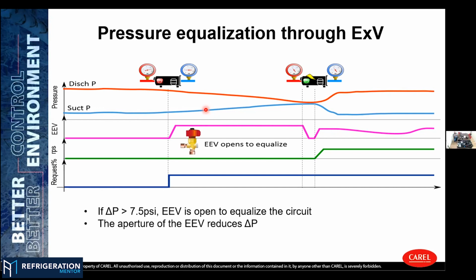So in some cases we can connect the valves to the condensing unit controller or to the rack controller in order to make these adjustments. In other cases, we can have, for example, a dedicated oil return valve open for a few seconds in order to make this pressure equalization. It depends on the application, but in most of them we try to make this equalization before starting up the compressor so we can extend the life of the motor inside the compressor.